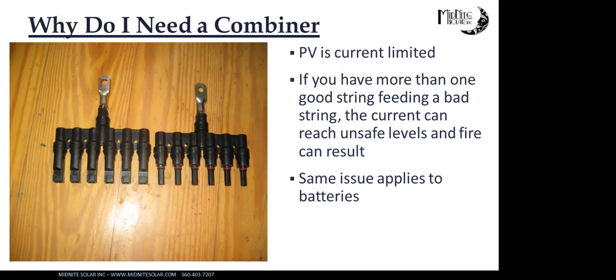But now let's say you have 5 strings, and each string is good for 10 amps. When one string shorts out, those other 4 strings are going to put 40 amps back into that one string. And now you've exceeded its safe rating, and it is going to heat up. It is going to catch on fire. So in general, it's mandatory to have combiners and overcurrent protection on 3 or more strings. I find it very handy even on 1 or 2 strings. It's just an easy way to disconnect things, troubleshoot things, make things safe downstream.